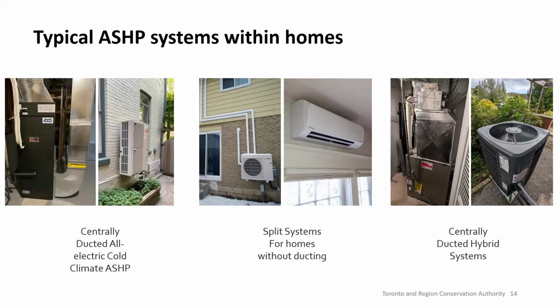Very similarly, an air source heat pump has an A coil too. So this system, although it looks exactly like a traditional furnace and air conditioner, is actually a furnace and a heat pump. The benefits are that maybe there are challenges in sizing the heat pump, or challenges in your duct sizes, so you're able to size the heat pump to meet a majority of your heating load, in some cases 80% plus, and the furnace works in really cold conditions.